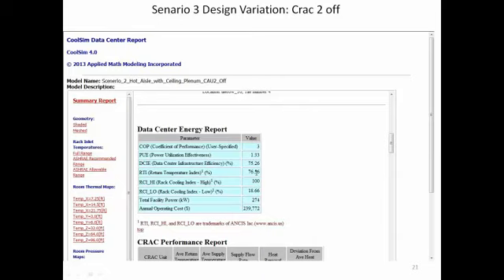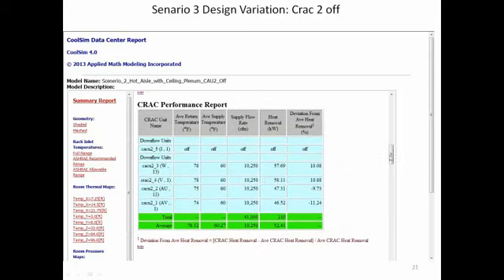So that's a reflection of the improvement in the ratios. And RCI high didn't change, which means we're doing a pretty good job with air distribution, because by dropping airflow down, you would think I'd start to get hot spots. We didn't. RCI low stayed about the same. So, and you brought supply temperatures to 60 degrees. They're even across 4 units. So that looks pretty good.